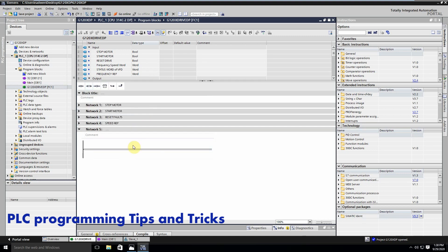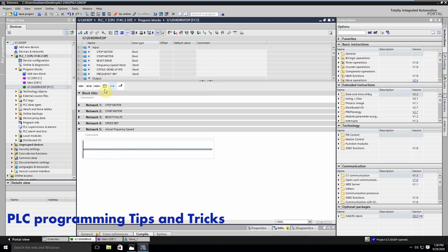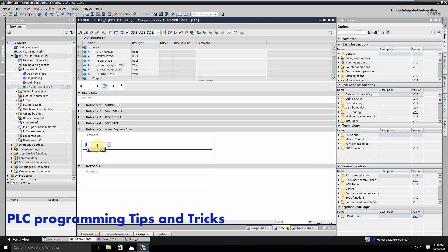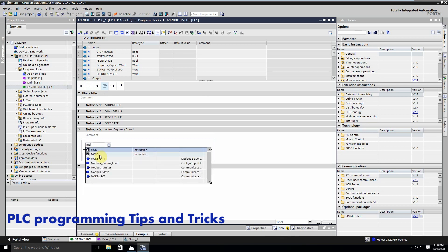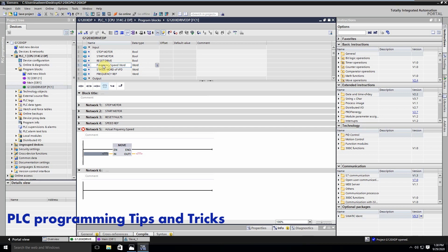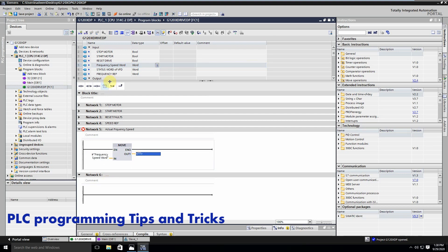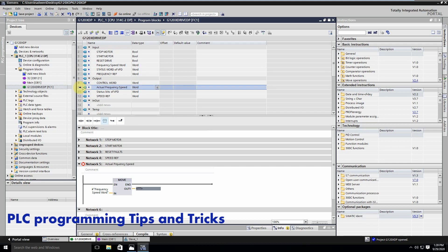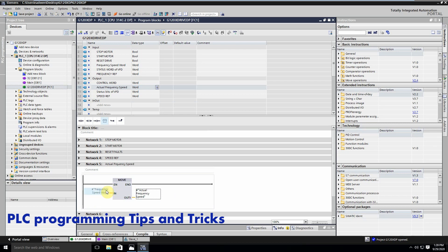We will go to Network 5 and write 'actual speed or reference'. Here we will use the Move command. We select the frequency speed word and drag and drop it on the input, and for the output we drag and drop the actual frequency speed word. Whatever data is in the frequency speed word will be moved into the actual frequency speed word.